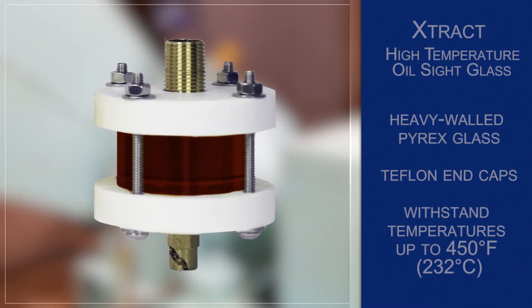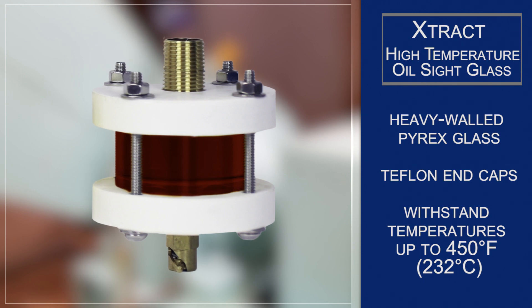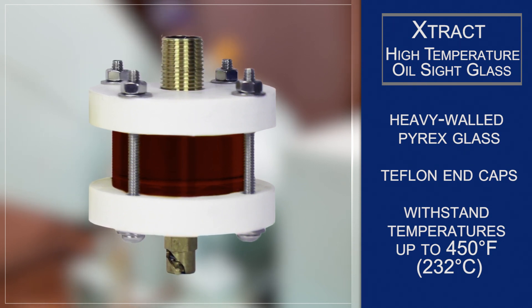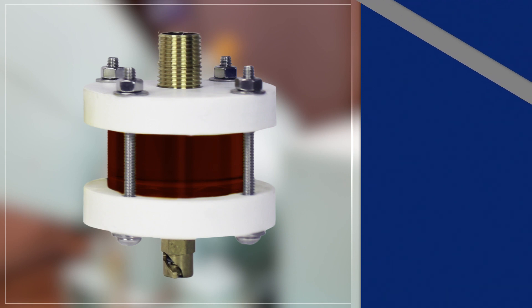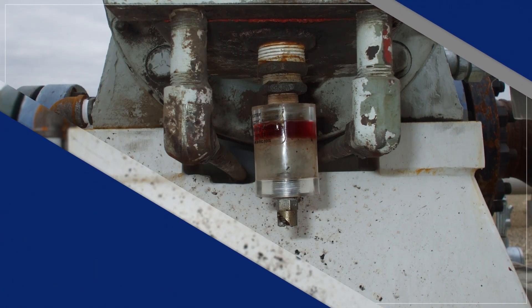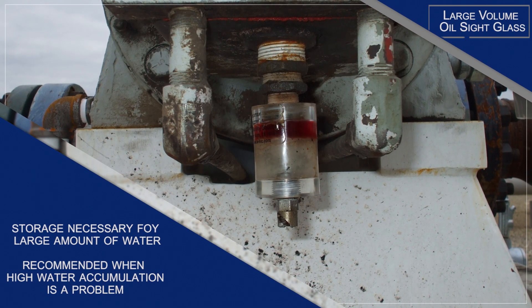The Xtract high temperature oil sight glass comes with heavy-walled Pyrex glass and Teflon end caps, making it suitable for use when the radiant heat from nearby equipment exceeds the temperatures that allow safe use of other oil sight glasses. It can withstand temperatures up to 450 degrees Fahrenheit.